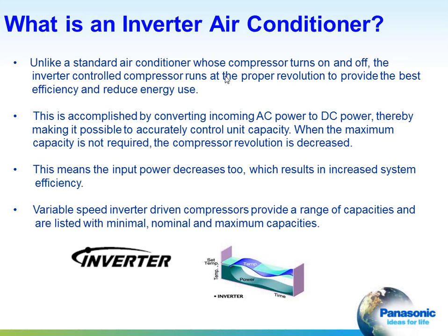Some of this efficiency is accomplished by the use of an inverter compressor. Unlike a standard air conditioner whose compressor turns on and off, the inverter compressor runs constantly, changing the number of revolutions. The RPMs provide the cooling capacity or heating capacity that's needed, and this gives us better efficiency and reduces energy use. The way that we control that compressor is that DC power is easier to control. DC motors are easier to control than AC motors. What we do is convert AC to DC power through an inverter. From there, we control that motor in the compressor to provide the RPM required to provide the capacity that's needed, again, in either cooling or heating.